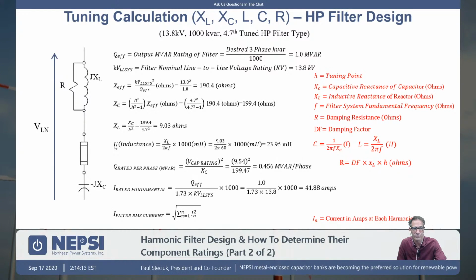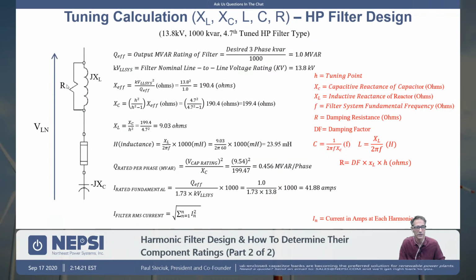A high-pass filter is exactly the same calculation. Really, the only thing that changes is coming up with this value of resistance, which is really determined during a harmonic study. We need to have a dampening factor when we're doing the study. We're coming up with a value of resistance. Remember, you always want to design first for notch filters. Try to see if you can get through a system and have a good performance with notch filters, because they are the simplest and most cost-effective filter design.